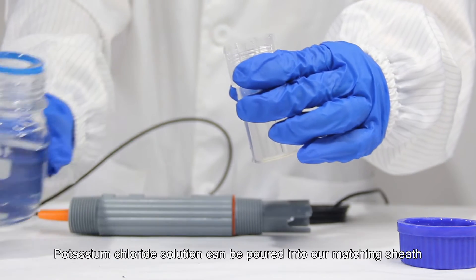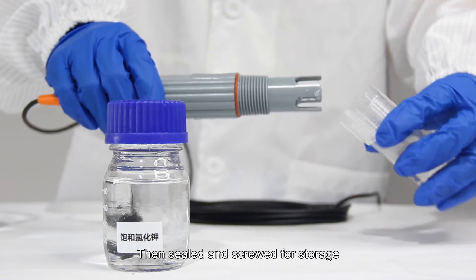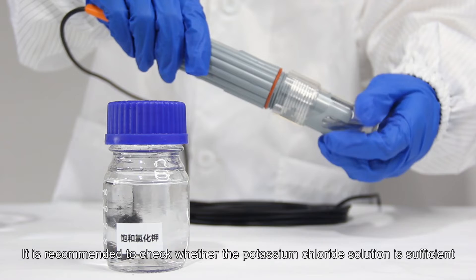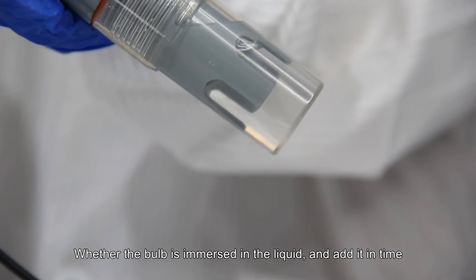Potassium chloride solution can be poured into our matching sheath, then sealed and screwed for storage. It is recommended to check whether the potassium chloride solution is sufficient and whether the bulb is immersed in the liquid.